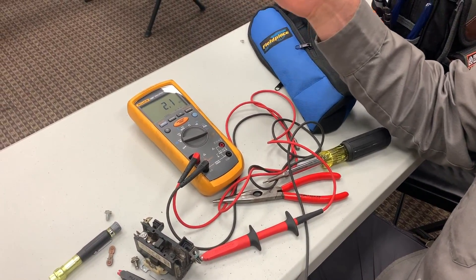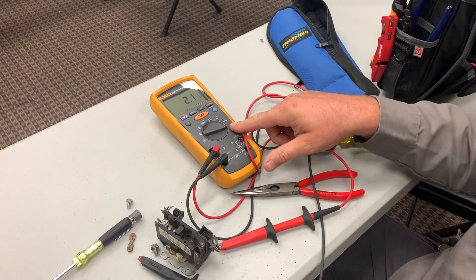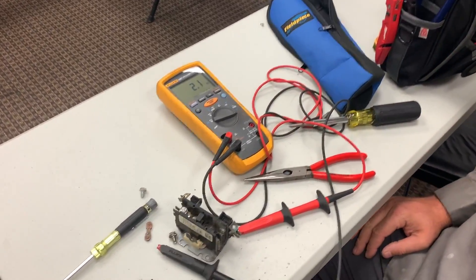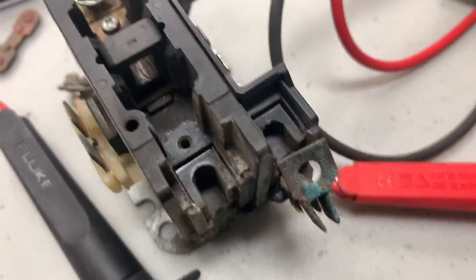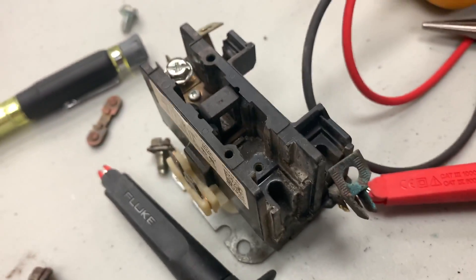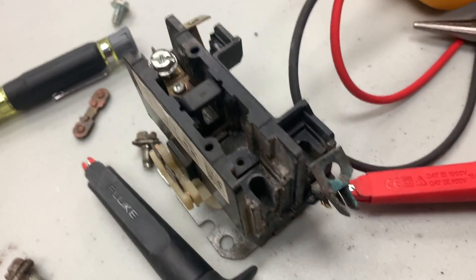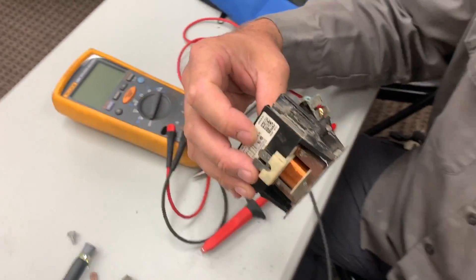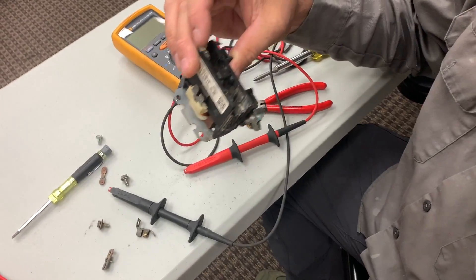You have millivolts, which I've not really had to mess with, and you have your insulation testing when you need it. So there's our diagnosis. We have some path through there even after cleaning it. I was just thinking maybe it's bridging through here, so I put contact cleaner on and wiped it all down. I didn't get a brush and get real aggressive, but it's a real thing. Yeah, that's really cool. Alright, cool.